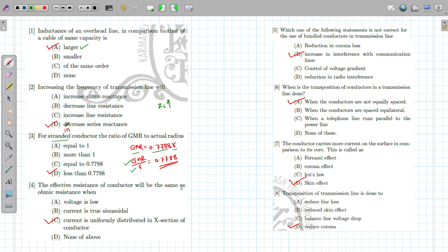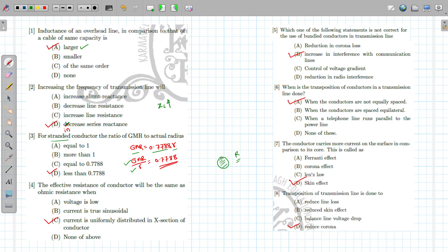The effective resistance of the conductor will be the same as the ohmic resistance only when the current is uniformly distributed over the conductor. If the current is uniformly distributed, the value of resistance will be the same at all points — the effective resistance will equal the ohmic resistance. Otherwise, the resistance value will increase due to the skin effect.